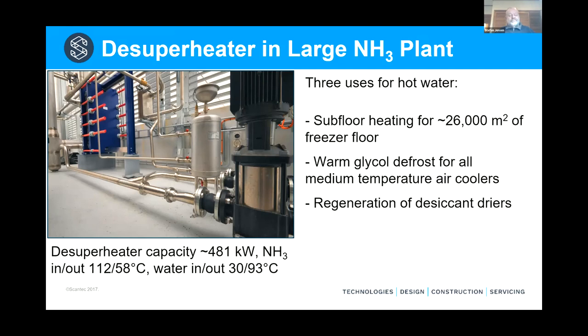And this is significant. In a 40 to 50,000 cubic meter cold store, an electrically regenerated desiccant dryer can consume up to 10% of the electricity consumption of the refrigeration plant that runs that cold store. So this is quite significant. I mean, a typical 40,000 cubic meter cold store with a low charge ammonia plant will take around 1200 megawatt hours a year. 10% of that is very significant.